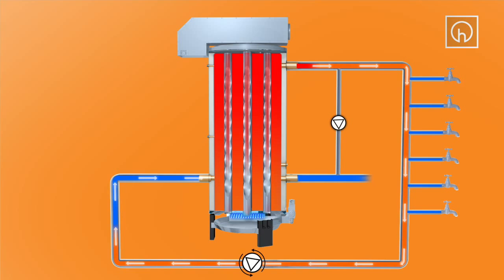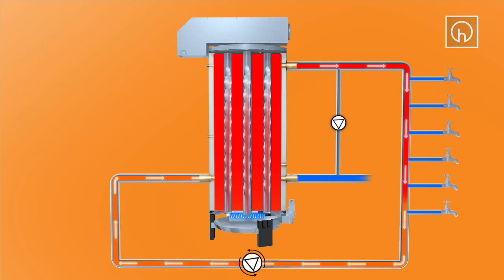Cold water at the top of the cylinder is replaced by rising hot water. Cold water at the bottom of the cylinder picks up heat and continues the cycle. The hot water system pump contributes to the thermodynamic effect by mixing water temperatures within the cylinder between flow and return connections.